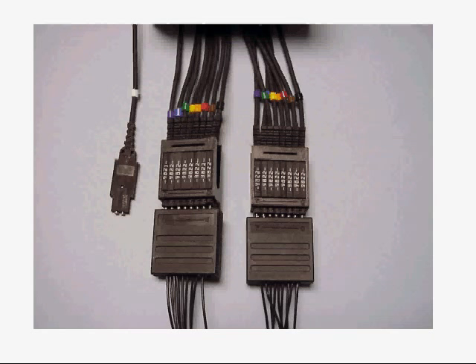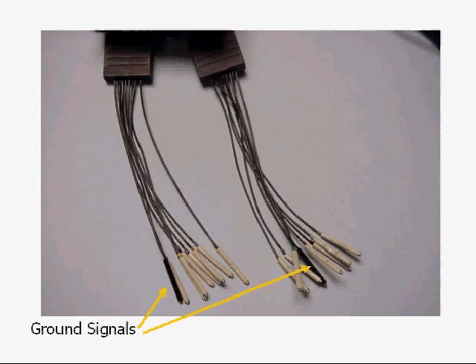Continuing down the cables, notice that each wire is color coded. The order of this color code should match the order of the acquisition pins at the end of the cable. Note that the color bands are in the same order. Also note that in each bundle there is one black connector. This connector is the common ground.